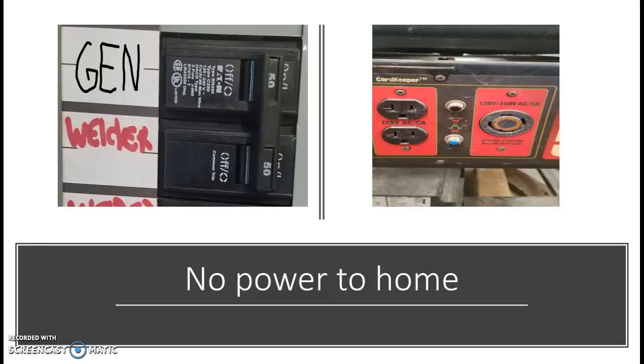If we have no power to the home with the generator running, check our generator circuit breaker in the main circuit breaker panel. Make sure that it is in the on position and that it did not trip. Next, check your circuit breakers on the generator itself. It has fault protection inside the generator.